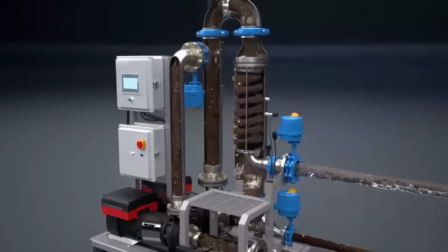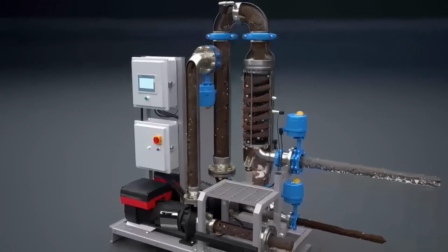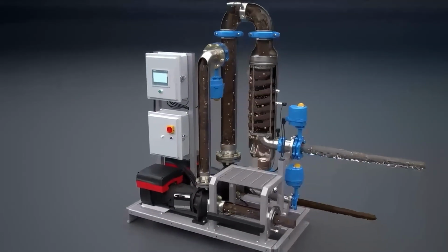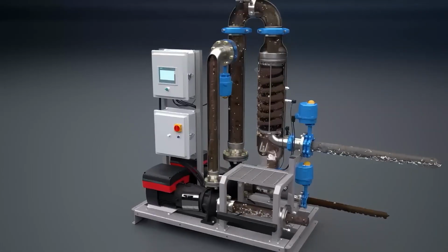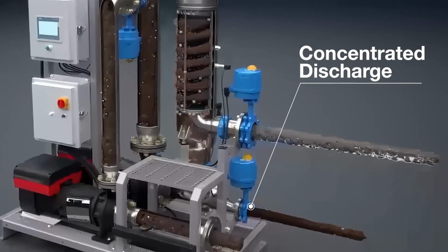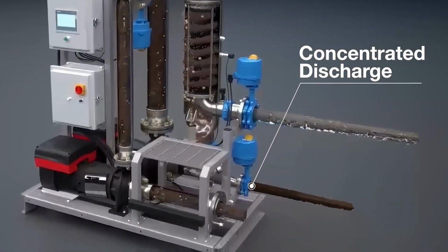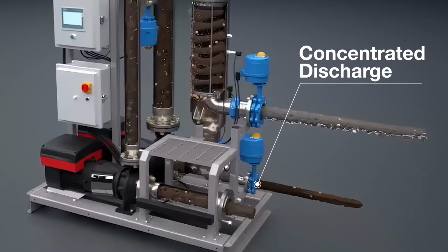The fluid that does not flow through the screen is pulled into the drive pump and sent back to the combined inlet to go through the filter housing again. This fluid contains particles that were rejected by the screen. The system continues to concentrate particles in the drive loop that are too large to pass through the screen.